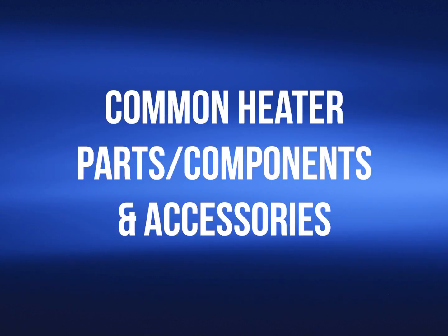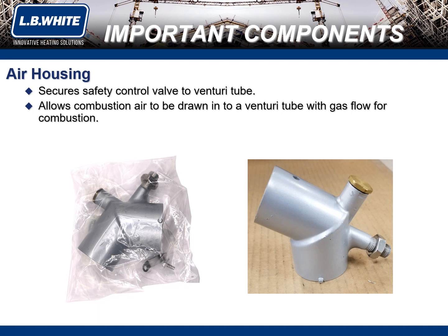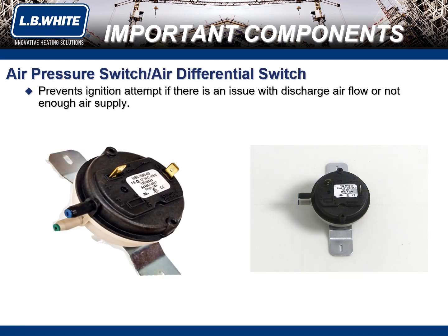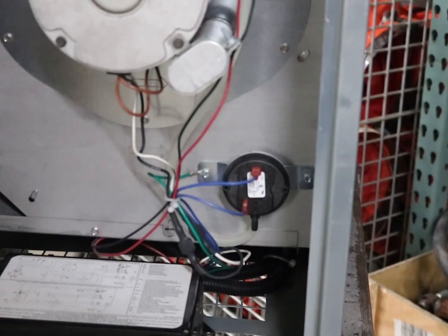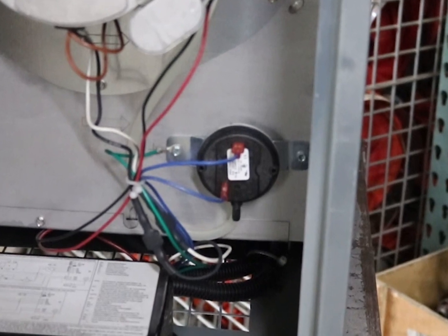In this lesson, we will go over some important components that appear in some or all LB White heaters. An air housing secures the safety control valve to the venturi tube and allows air to be drawn into a venturi tube with gas flow for combustion. An air pressure switch or differential switch ensures that the burner's fan motor is operating at the proper speed to ensure a safe startup before ignition occurs.